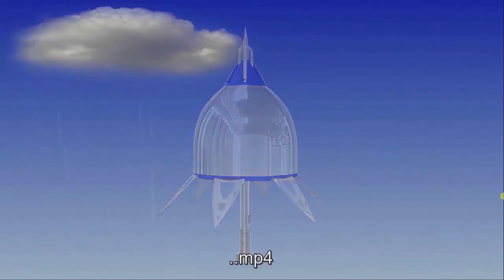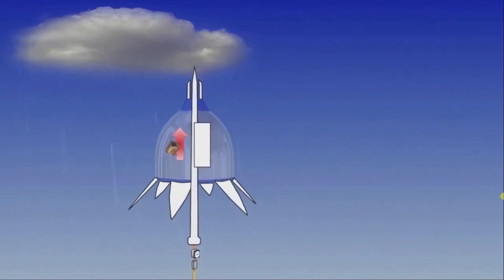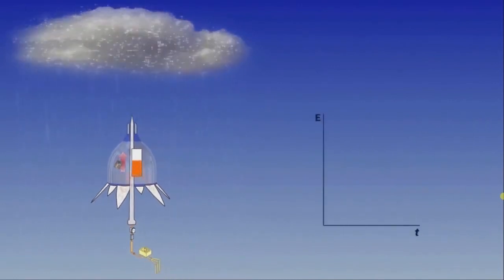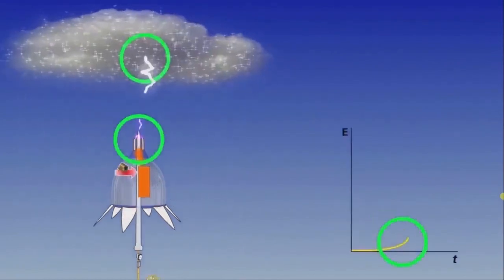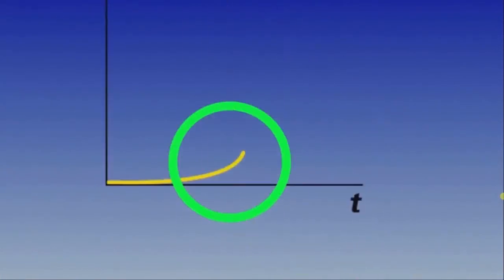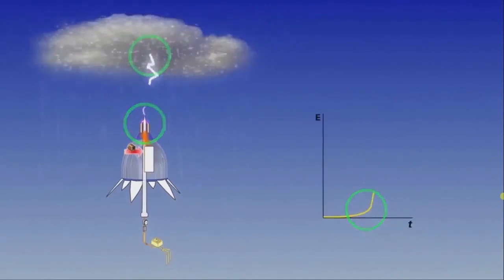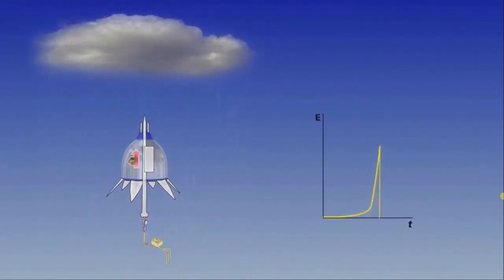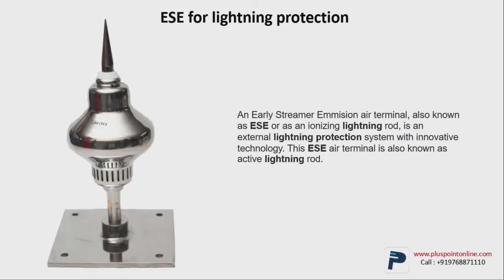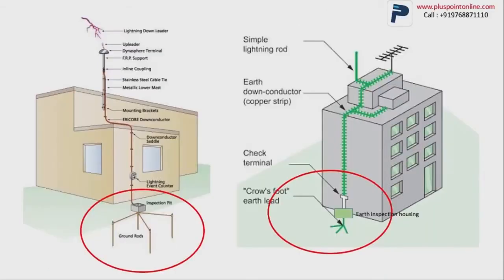In this animation, you can see a lightning rod, which is also called an active lightning rod. One part of the rod is facing towards the ground and the other to the sky. As the weather becomes worse, it charges itself. As you can see the weather getting worse, there's a spark getting formed in the cloud, and also on the lightning rod, there's sparkling. As soon as the lightning strikes, the rod attracts the lightning towards itself and transfers it to the ground. This process is called the ESE lightning protection system. This is a great technology. I won't get into the depth of it, however, I've tried to cover every aspect of it. Here you can see that both the systems have one thing in common, which is grounding, which includes the inspection pit and ground rods. The copper strips will remain common, but the top rod, as discussed, will be different.